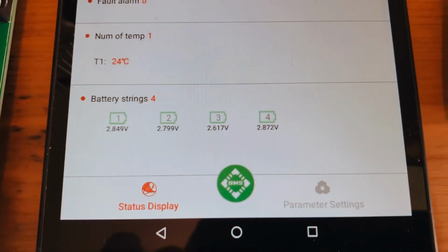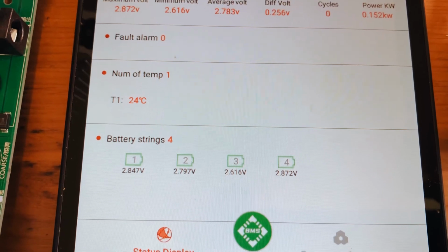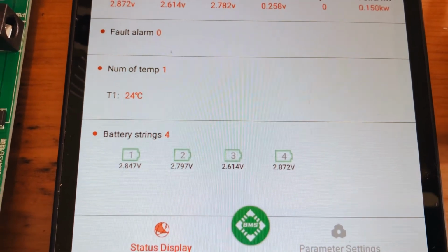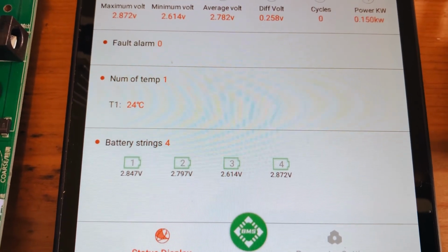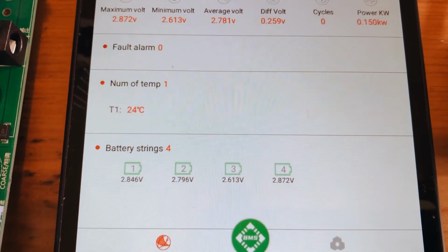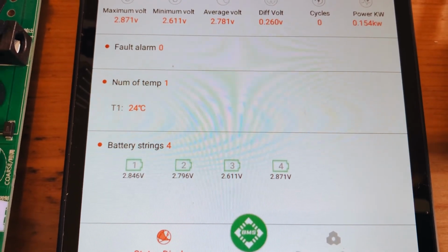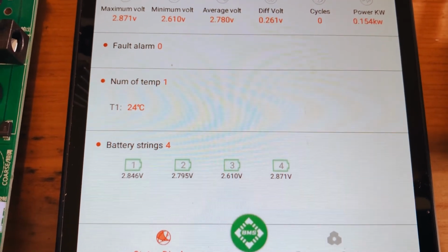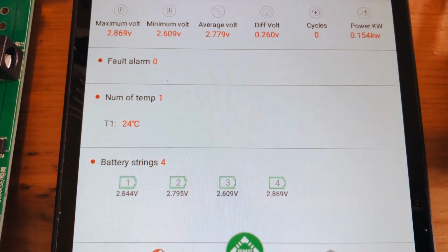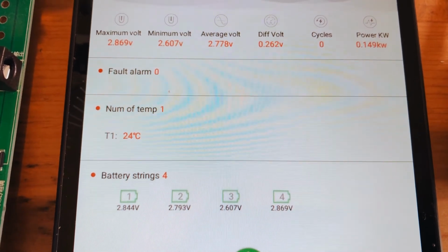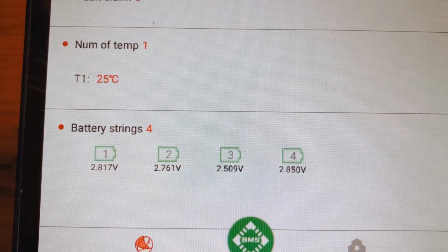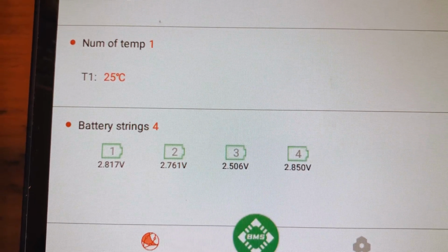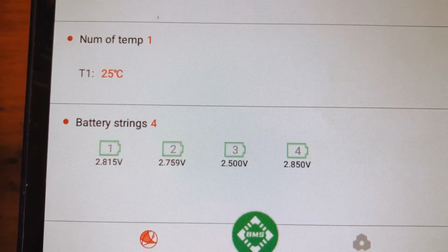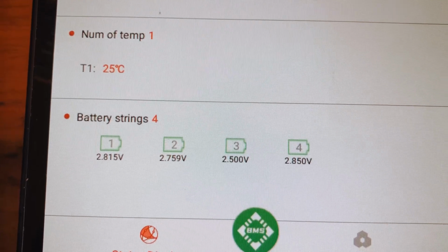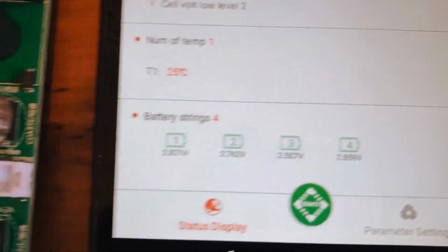and dropping quite rapidly on cell number 3. It's 2.61 something volts at the moment. We're expecting within just a few minutes it will reach 2.5, at which time the BMS will actually cut it to keep the battery safe. All of the cells have dropped below 2.9 volts now. So the lowest is 2.5, which is the point at which the BMS actually cuts off. As we can see, this has just cut.